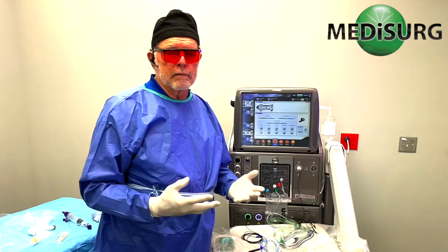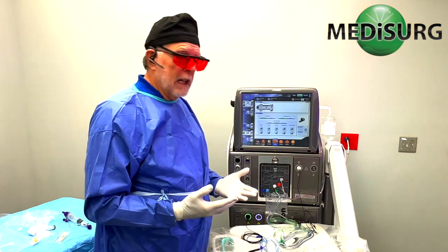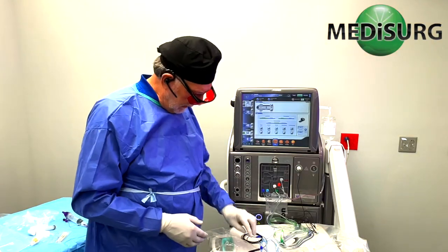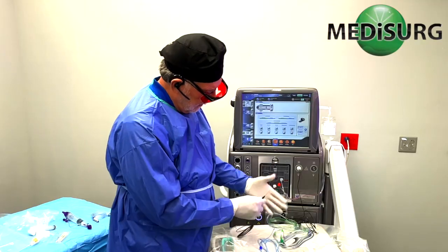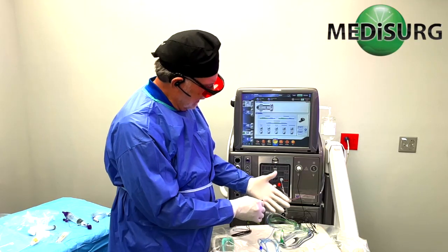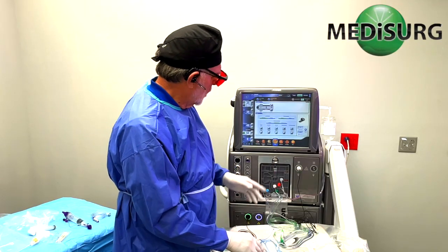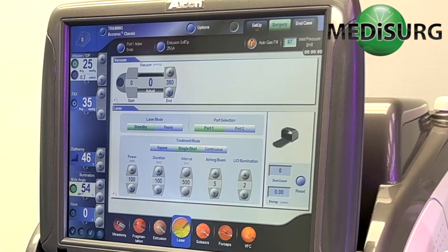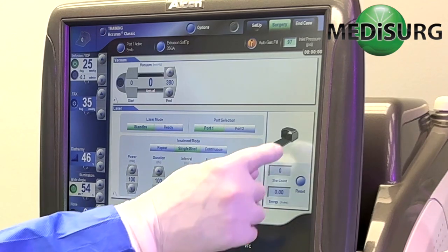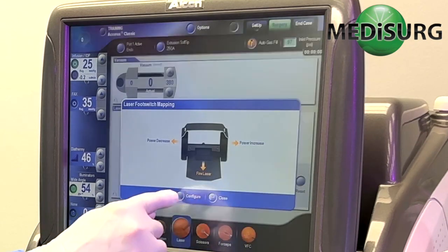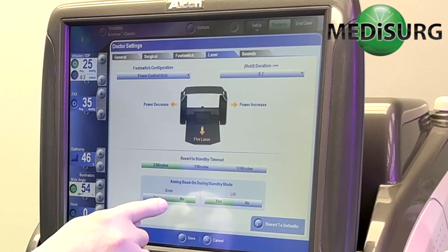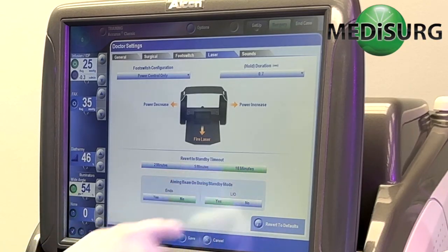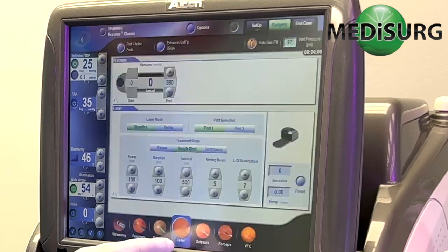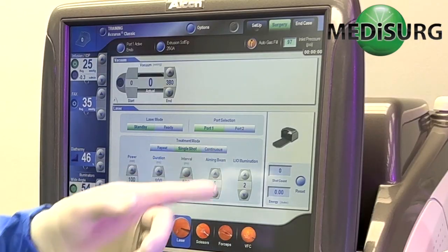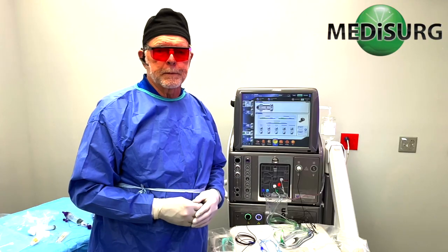And if you had the volume down, you would never know, but the laser is no longer activated, so you don't see any of the red light. So how do you fix that? Foot pedal, configuration, and then select 10 minutes. Then save. So now when you activate it and go to the ready state, it'll be ready to go.